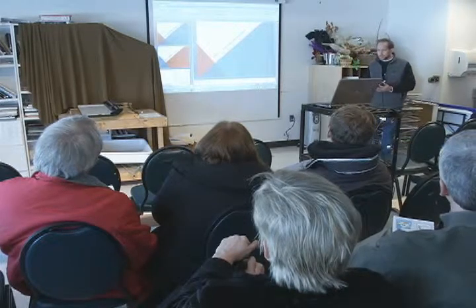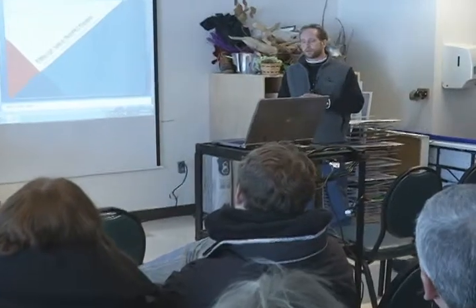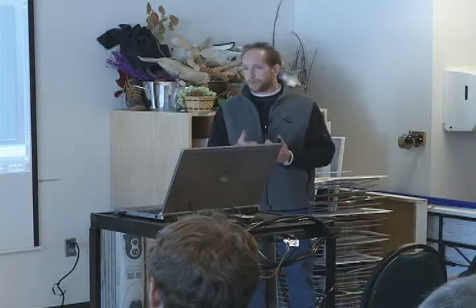Now, we do check out furnaces. We make sure furnaces are functional, and they don't have any of what we call little telltale signs of problems within it. We have a list in our guidelines that tells us which way to go on that. Certifications would be required if we find something on that list. Usually the telltale sign is a furnace that's burning with a really wild flame. A nice blue flame is a perfectly tuned furnace. When it's orangish red and very wild and rapid, that's a telltale sign that the furnace is either out of tune, it's got a cracked exchanger, or it's not getting the amount of air that's needed to get that blue flame, which goes back to tuning. We ask for certifications on a furnace if we see signs of something wrong with it.